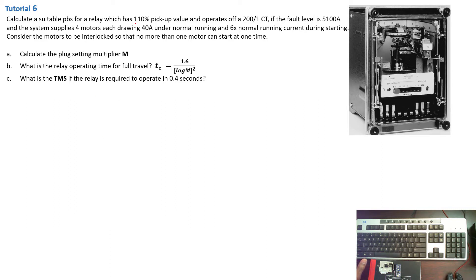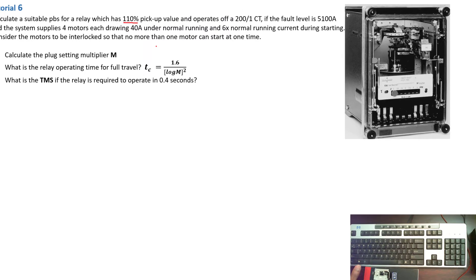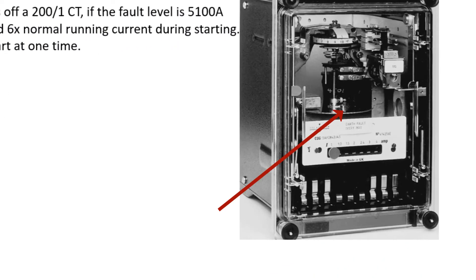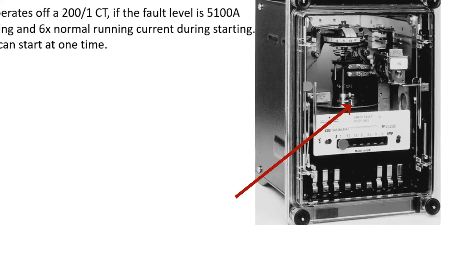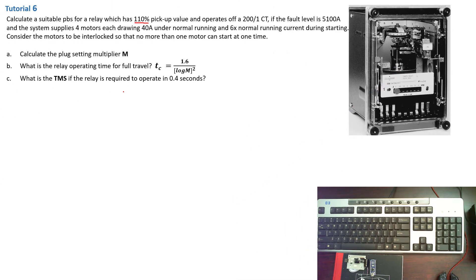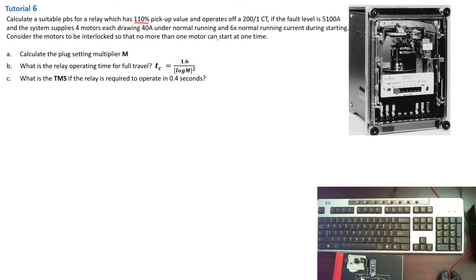Already from here, we can see that the relay has a 110% pickup value. So that is the settings for the disk. So that means we have to consider solving it for overload condition because if the relay had a 90% pickup value, we will be solving for normal condition.